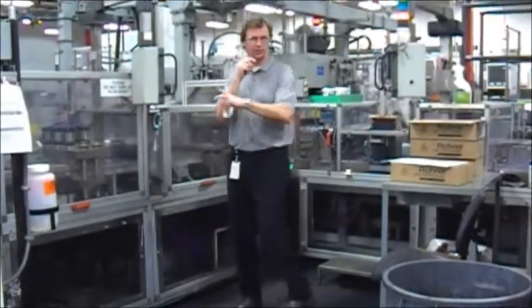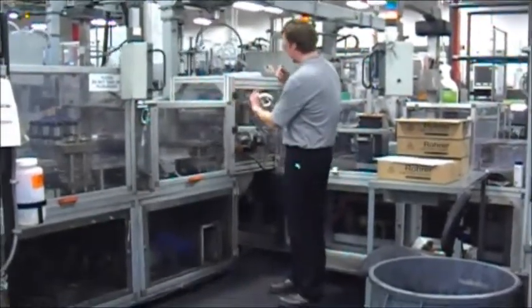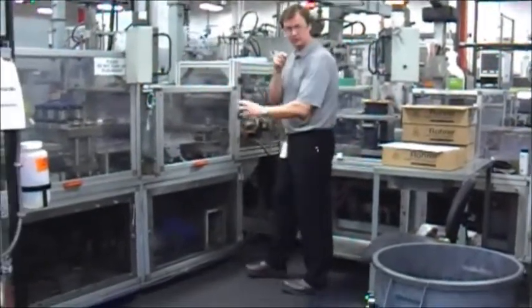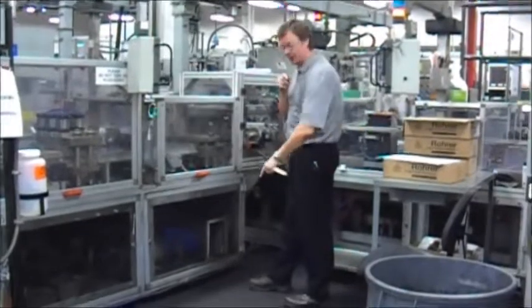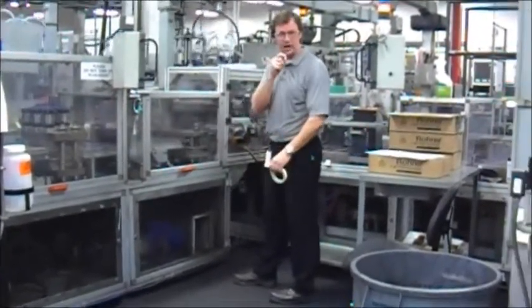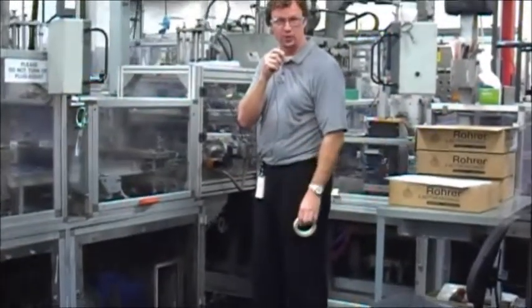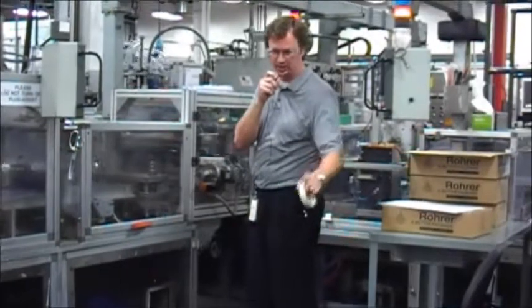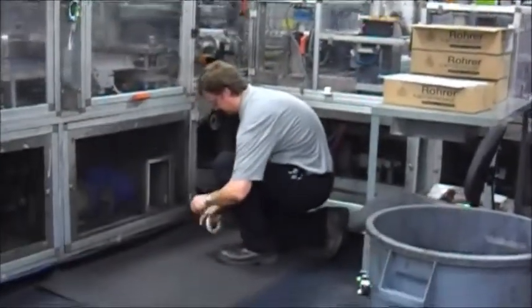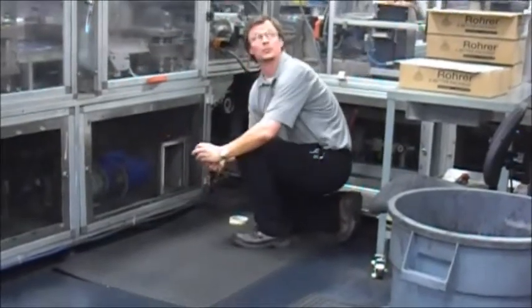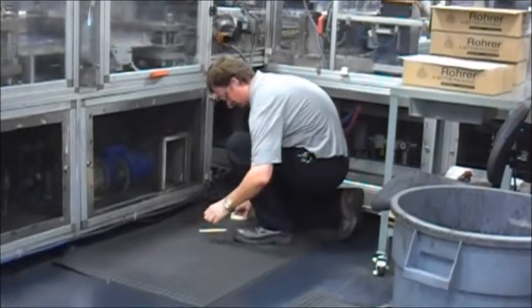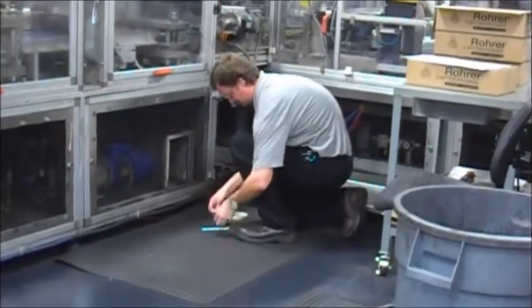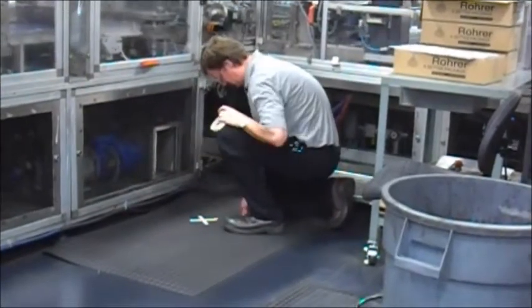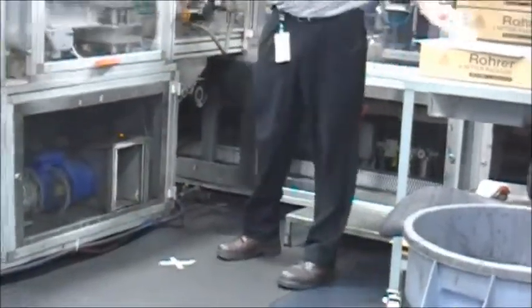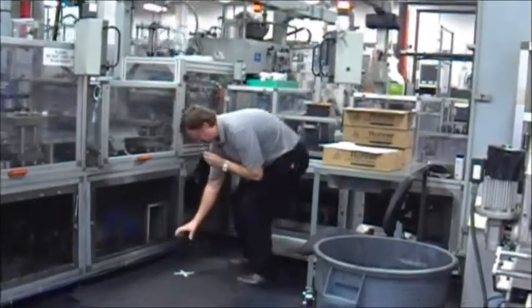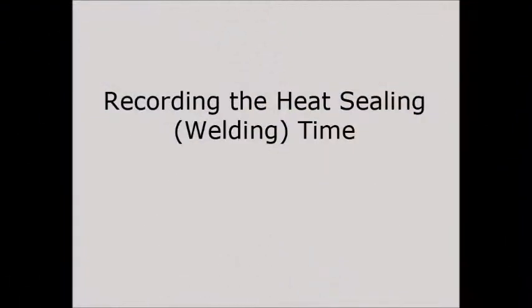On this piece of equipment, as I said earlier, the operator is actually standing away from the RF sealing table. But here's his normal position. So typically we would also measure where the operator resides. So in this case I'm going to put an X on the floor to indicate where we'll put our probe and our stickman. The X on the floor is where the head of my probe will be above.